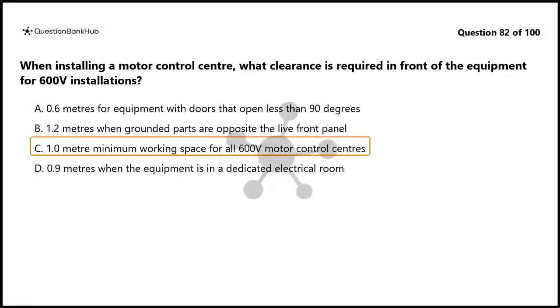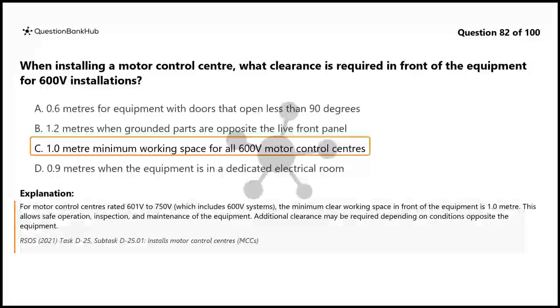The correct answer is C. 1.0 meter minimum working space for all 600 volt motor control centers. For motor control centers rated 601 volts to 750 volts, which includes 600 volt systems, the minimum clear working space in front of the equipment is 1.0 meter. This allows safe operation, inspection, and maintenance of the equipment. Additional clearance may be required depending on conditions opposite the equipment.